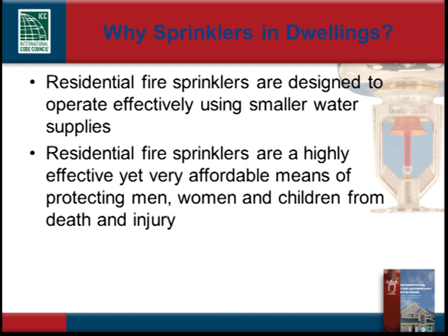Residential fire sprinklers are designed to discharge less water and operate for a shorter period of time than commercial fire sprinklers. They flow less water for a shorter duration because their goal is to provide for occupant safety and safe evacuation. There are no moving parts to wear out, and they do not need mechanical or electrical devices to initiate them — they simply react to the heat from a threatening fire. The simplicity of residential fire sprinklers makes them reliable and effective life safety devices.